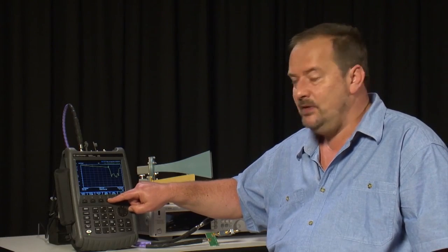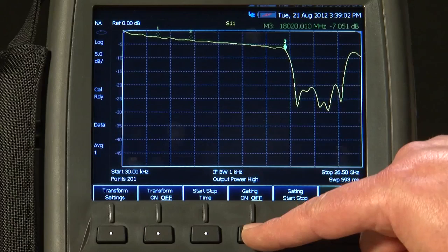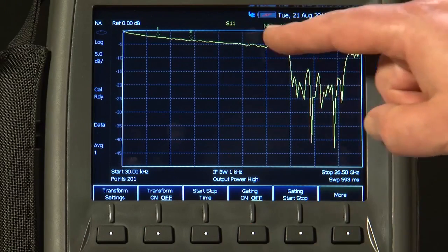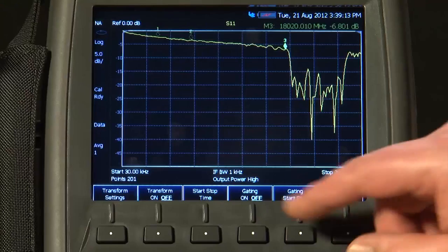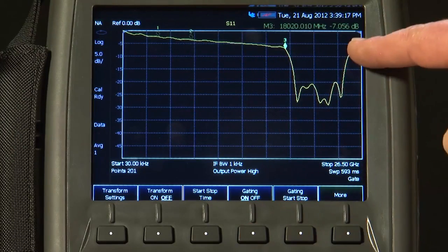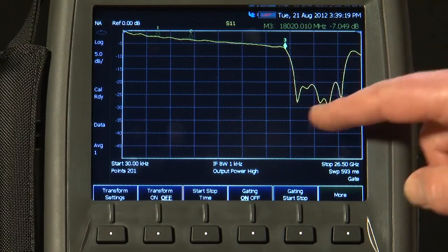In fact, the gating on-off button is still available even in frequency domain. So I'll show you that is the response with the gating turned off. And you can see the ripple here caused by multiple reflections from the non-50 ohm discontinuities in the measurement path. If I put the gating back on, it smooths all of that out, and now we are truly measuring the return loss response of just the filter and not the rest of the measurement system.